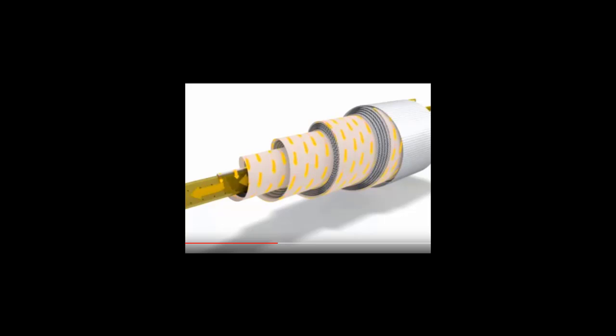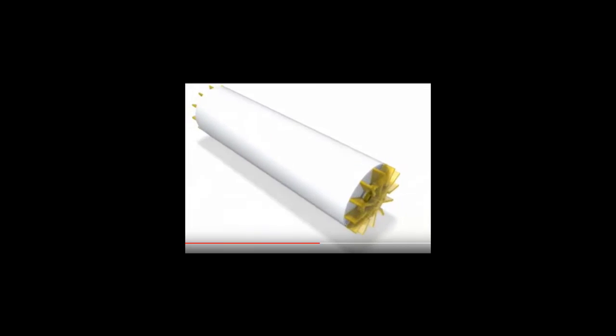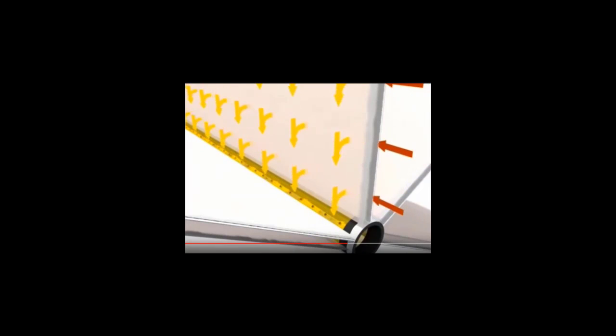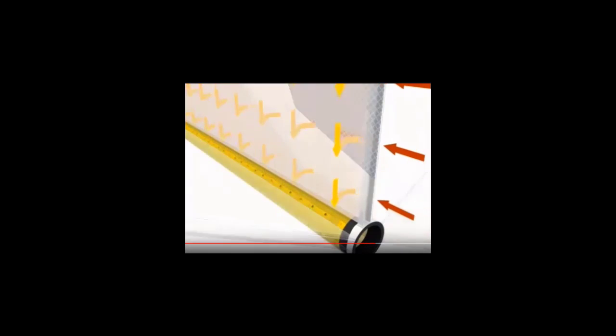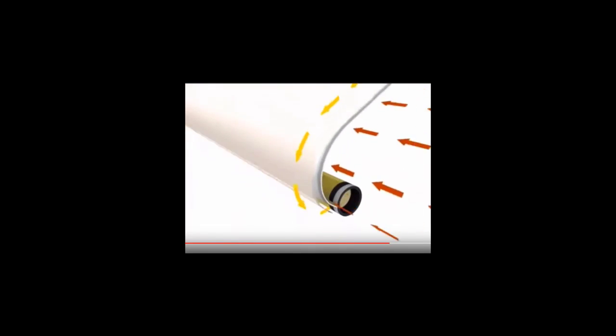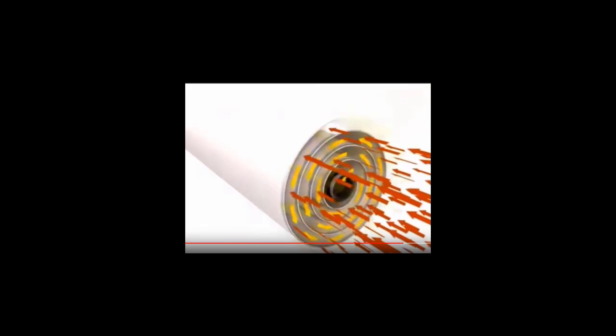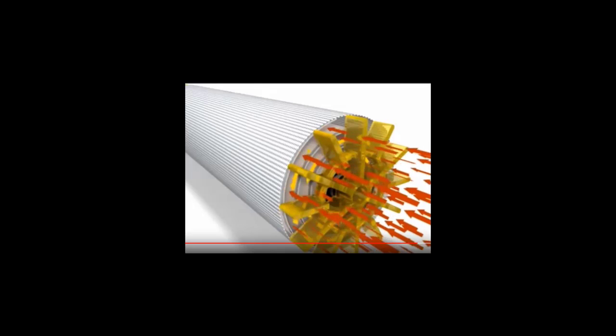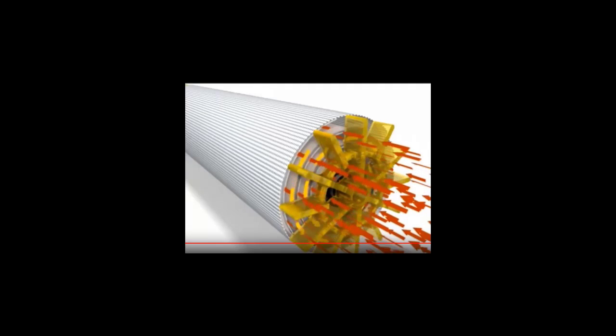The membrane is constructed such that the permeate is transferred to a perforated central tube known as the permeate tube from which it leaves. It may be easier to understand how this separation takes place by unrolling the spiral membrane, allowing a further look at the membrane construction. The feed can only enter where indicated since the membrane sheets are glued to form membrane envelopes that contain a spacer which ensures that the permeate is transported to the central tube. The spiral module is constructed by attaching a number of properly glued membrane envelopes to the central tube with a spacer in between to allow room for the feed flow, and then by rolling the envelopes such that the spiral is formed. At the outlet end of each spiral, an anti-telescope device is placed to prevent the pressure of the liquid from deforming the membrane shape.